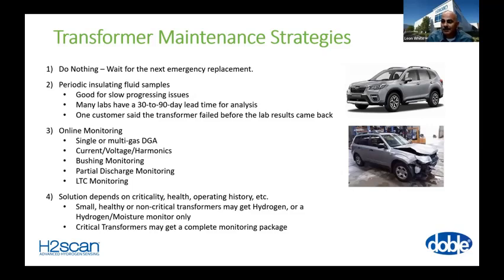Being such a critical component, and one that's certainly harder to get, going back to Moses' presentation again, online monitoring is a great strategy to employ to have the transformer let you know when there's a problem, so hopefully you can fix that problem before the transformer fails. What's very popular, as Mose also indicated, is periodic insulating fluid samples. We've moved away from the term oil sample as we move into alternative fluids, the esters and so forth, so now we're calling them insulating fluids. Typically people are taking those once a year, probably on average. Critical units, a lot of people will sample quarterly.